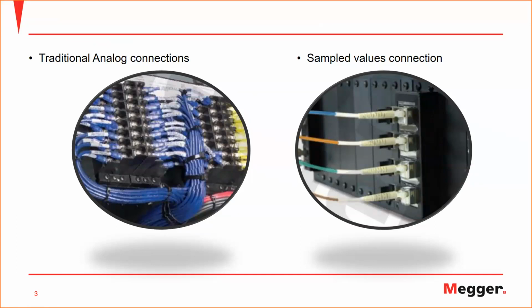And to help us achieve this transition from the traditional analog connection that we've been using for more than 100 years now to the digital world, there are some standards that we need to understand or follow to help us achieve this goal very efficiently and overcome many of the challenges that come with this shift. So when we talk about sampled values, mainly the IEC 61850 standard that introduced them will pop out, but IEC 61850 is a very broad standard and keeps growing and growing. So we have to go to the specific parts in that standard and also other standards that touch the subject of sampled value directly.